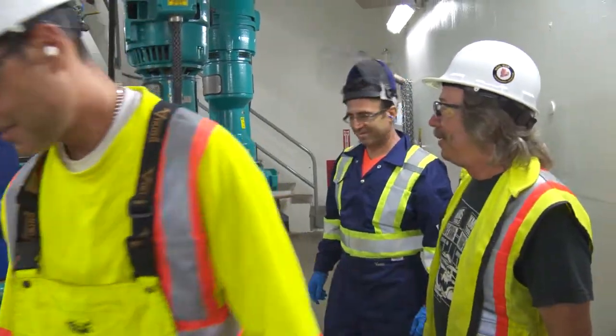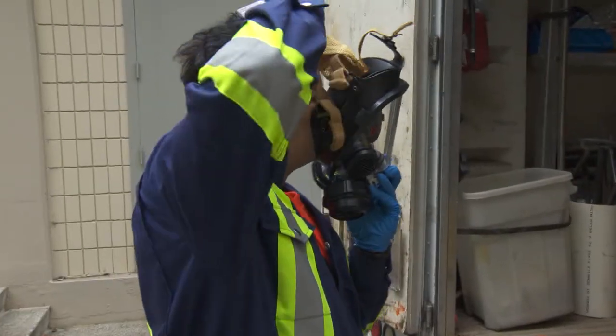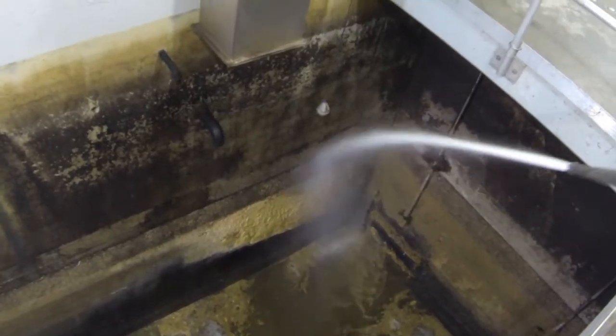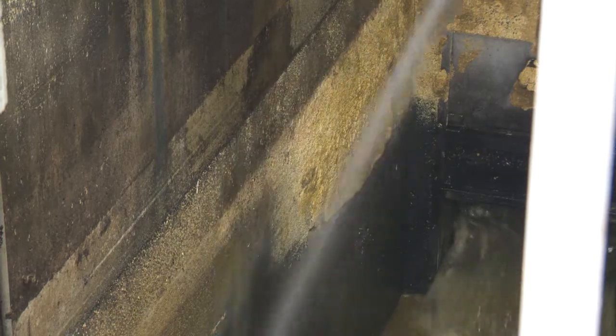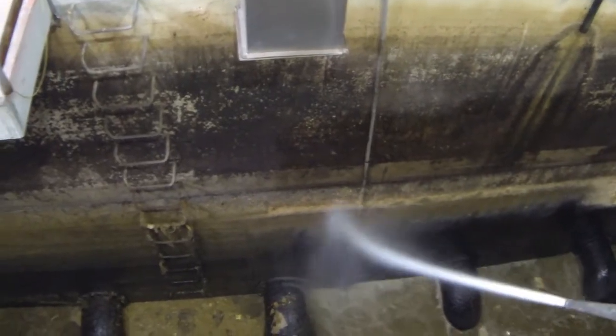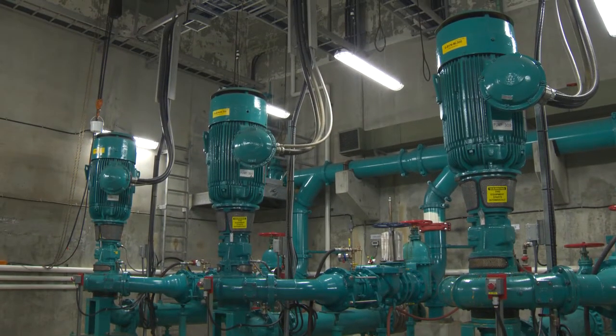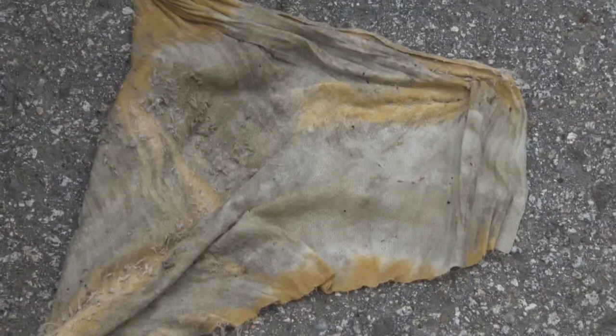Today they're at the Port Moody pump station for routine cleaning and inspection. Joe will head into the wet well side of the building. It contains a small pool — not for swimming in; it's fed by incoming sewage. That's grease buildup. If you don't keep up on it, it'll just get thicker and thicker. These pumps have impellers inside, basically spinning fans that draw the sewage up and onward. All this stuff has to be able to pass by — that's where all the towels and extra socks you can't find end up. They're in here.